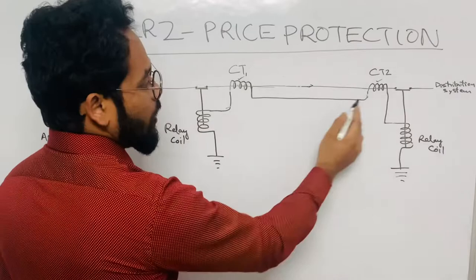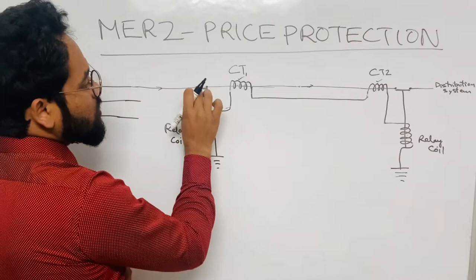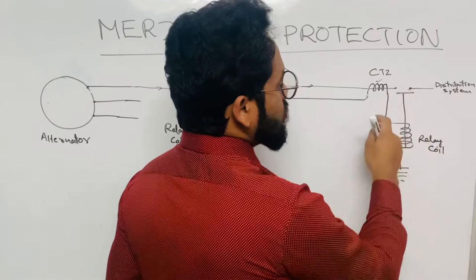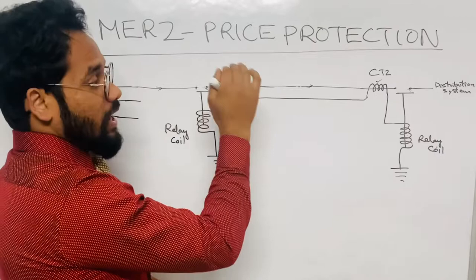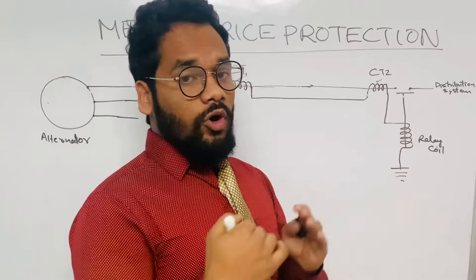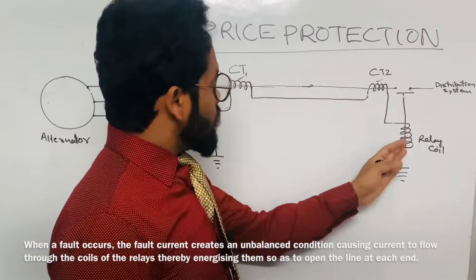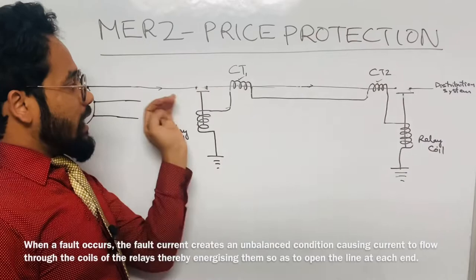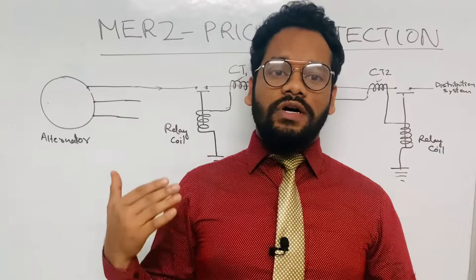When current flows, both relay coils will be energized. Because of the energization of the coils, both contactors will open — on both the source side and the distribution side. When these contactors open, current will not flow to the distribution system. This is the desired outcome, since there is a fault in the system and we don't want current flowing to the distribution system. The Merz-Price protection system achieves this by opening both contactors, cutting off current flow during the feeder fault condition.